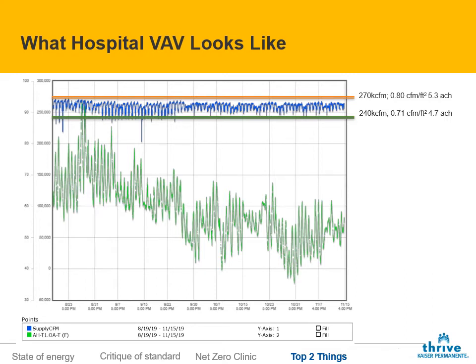Design capacity for this system is 350,000 CFM, which is about a CFM per square foot, or somewhere in the neighborhood of 7 air changes per hour for the whole volume of the building. That's the design peak capacity. And on that note, it's a good thing that we have VAV here because even on the 90-degree days, we don't need that. We don't need full capacity. We only really use 80% of that, right? We're running at 0.8 CFM per square foot or 5 air changes, for the volume of the building.